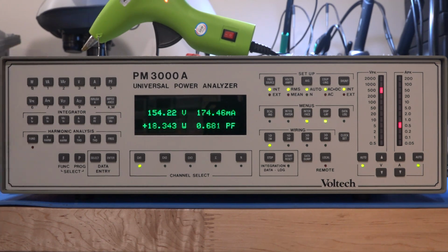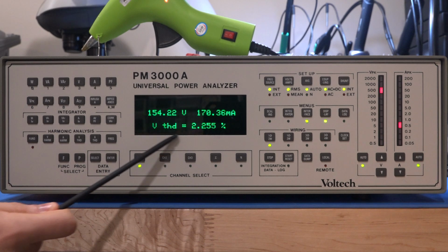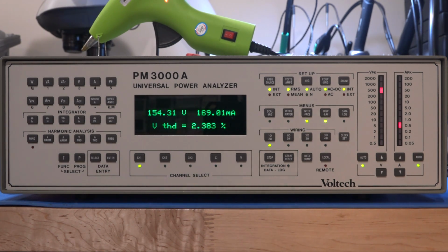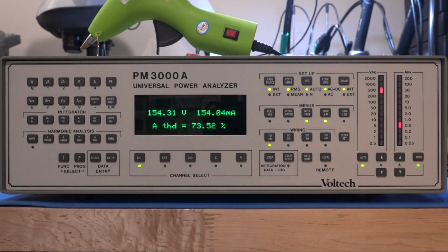But what you can also do is look at the harmonics. So for example, the total harmonic distortion on the voltage is about 2.2%. That's essentially the noise of this instrument, really. It doesn't give you very accurate results below 2%. So yeah, it doesn't really have that much distortion on the voltage line. But if I go under the amps, you can see that the amps THD is 73%, which is quite bad, meaning that there's a lot of harmonic being present on the current that this component here is actually consuming.